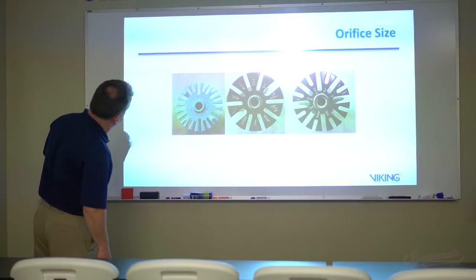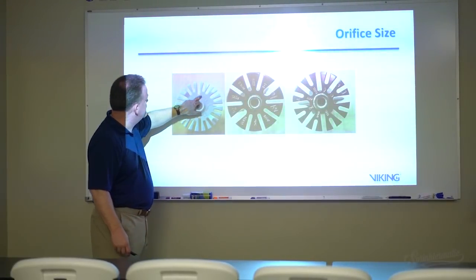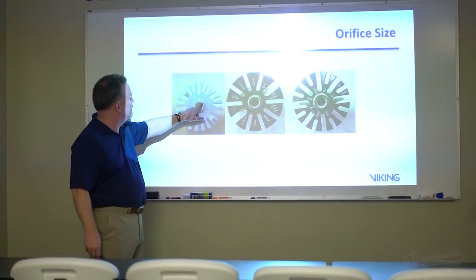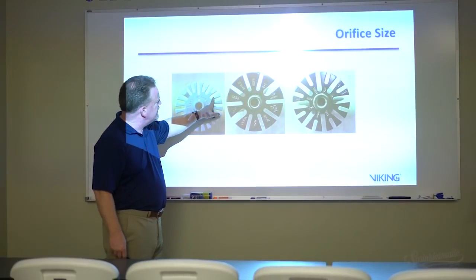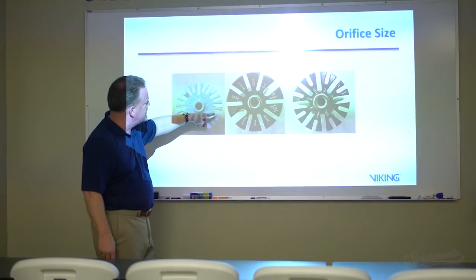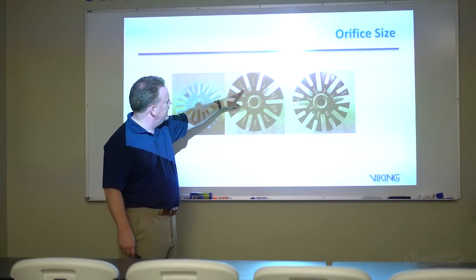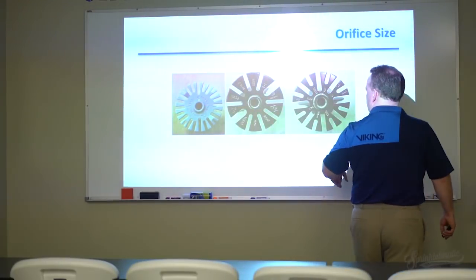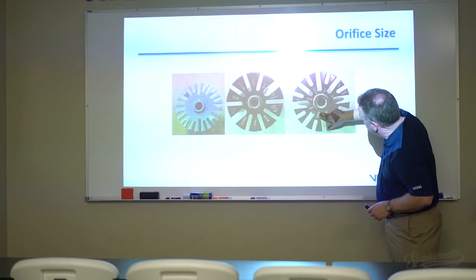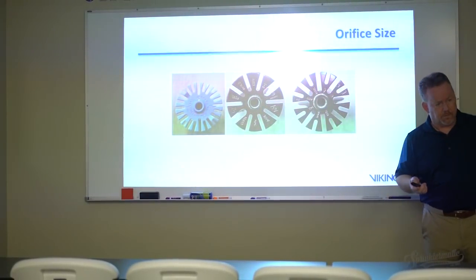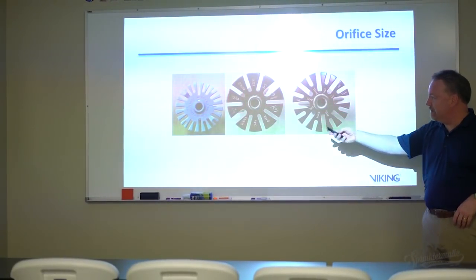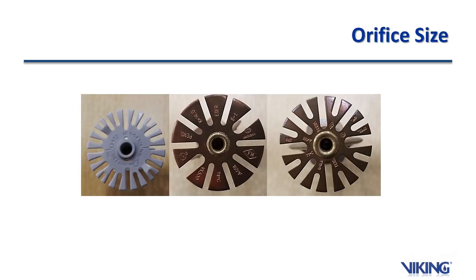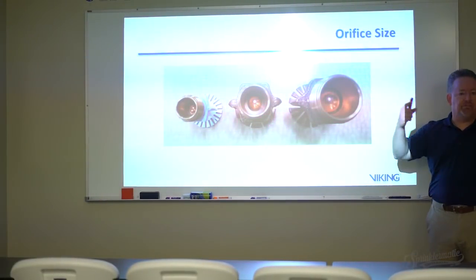Looking at the three sprinklers: the VK 472 has a K factor of 5.6 to 5.8; the middle one — an ESFR, VK 500 — has a K factor of 14; and the one on the far right has a K factor of 18.6. So we have K 5.8, K 14, and K 18.6, and they go even bigger than that.